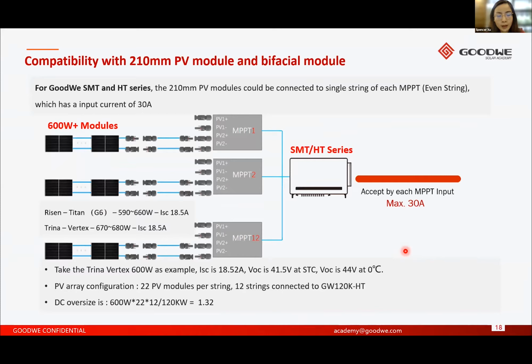While for the 210 millimeter PV modules, we offer a single string connection for each MPPT solution so that we can have a maximum input current of 30 ampere. Now let's take the Trina Vertex 600 watt and GoodWe 120 kilowatt HT as an example. As we can see, the short circuit current of the Vertex is 18.52 ampere, while the open circuit voltage is 41.5 at STC. So after some calculation, we can have 22 PV modules per string, and 12 strings are connected. And then we found that we still can have 132% DC oversizing.